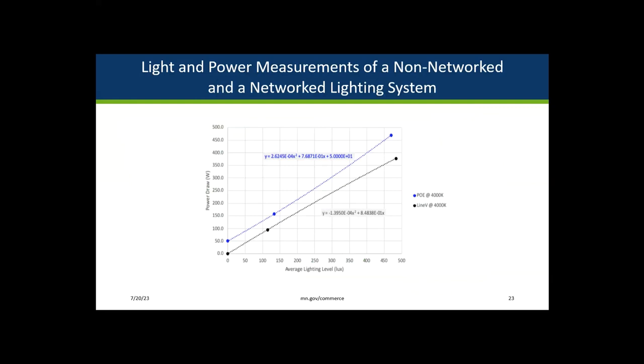This graph shows a comparison of two lighting systems in identical classrooms. One lighting system is a typical AC-powered lighting system controlled by a wall switch and occupancy and daylighting sensors, while the other classroom is a PoE luminaire level network lighting system with two occupancy sensors and a daylighting sensor. The graph shows how the power draw of both systems increases as the brightness levels of the lights also increase. Since the slopes of the two lines are parallel, the power demands of the LED lamps in the two classrooms are nearly identical. However, looking at the y-intercept, we can see that the baseload power of the PoE network equipment is about 50 watts, while the baseload power of the AC system was measured to be about 3 watts.